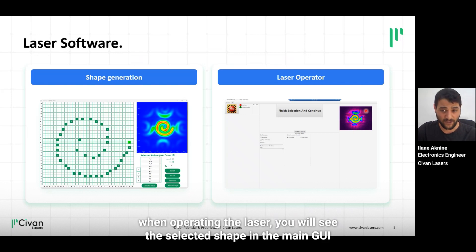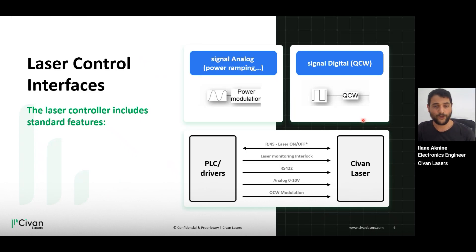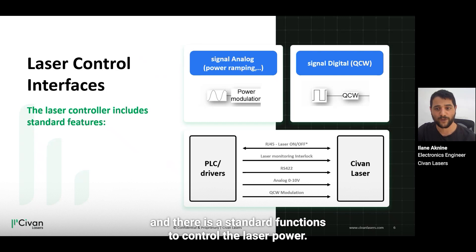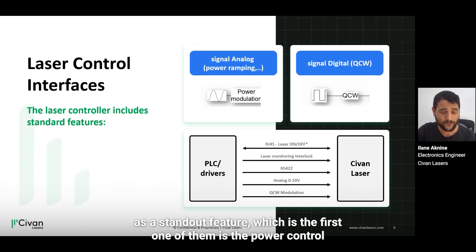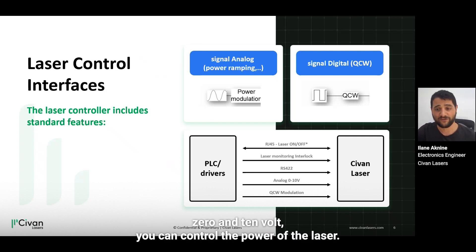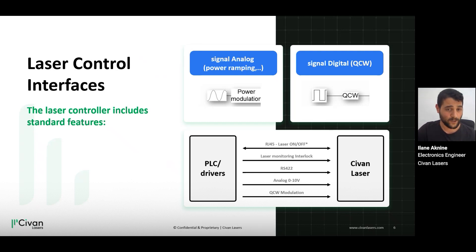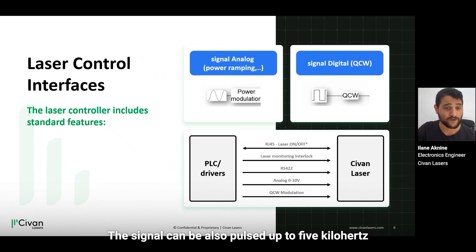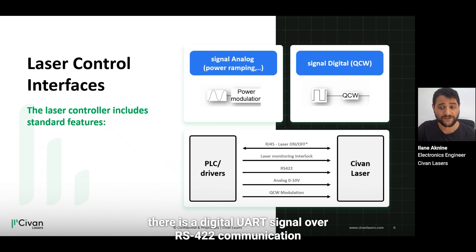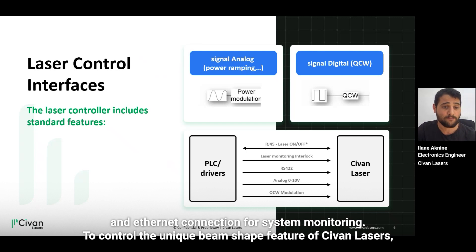As feedback when operating the laser, you will see the selected shape in the main GUI. The laser control interface is very simple, and there are standard functions to control the laser. The first is power control: with an analog signal between 0 and 10 volts, you can control the power of the laser. Another signal is the laser enable — a digital signal that turns the laser on and off. This signal can also be pulsed up to 5 kilohertz if QCW operation is needed. For beam control, there is a digital UART signal over RS422 communication and an Ethernet connection for system monitoring.